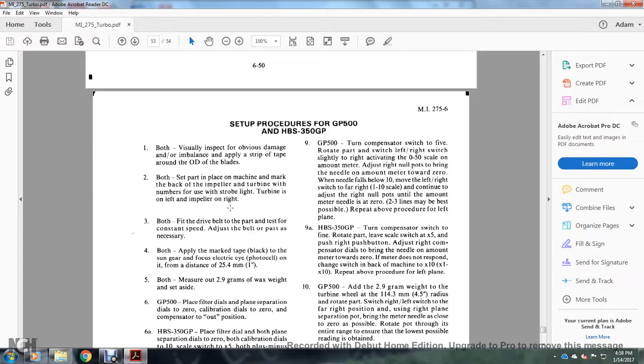Alright, your setup procedure for the GP500 and HBS350 GP. Both: visually inspect for obvious damage or imbalance. Apply a strip of tape around the OD of the blades. Both set in place on the machine. Mark the back of the impeller and turbine with the numbers for use with the strobe light, with the turbine on the left and the impeller on the right.